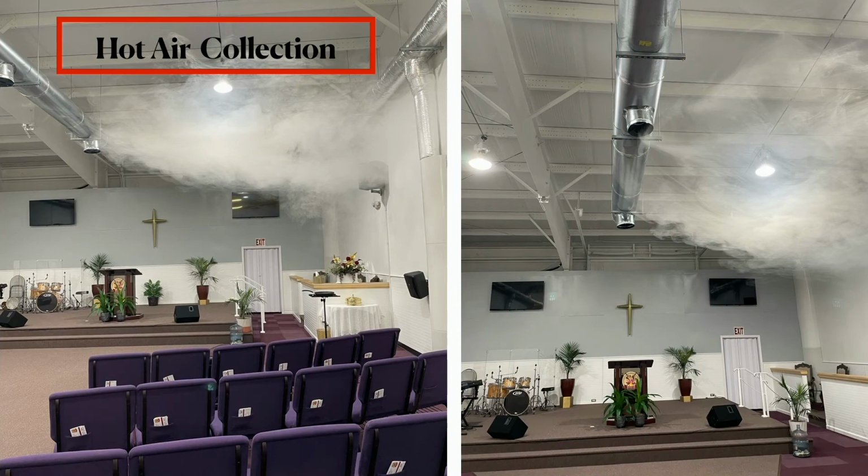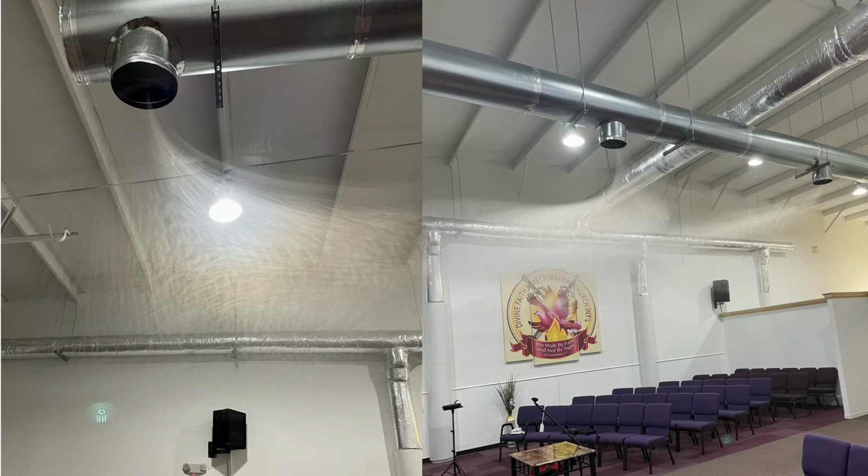Of course, now the smoke bomb has finished burning, so that means 40 seconds has passed, and you can already see that this stuff is starting to be pulled over to the collection header. In this diagram here, you can see the first two nozzles here picking up the smoke. Okay. The next diagram, you can see the zones actually created overhead. There's no cross mixing. You're not going to get cross mixing in between zones here. This is going to avoid the cross mixing in between the zones.